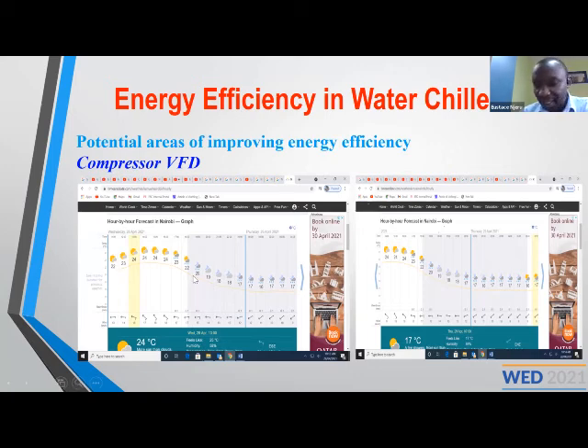You find that most chillers don't operate at full load always, because their operation is affected by the requirements of the cooling rooms and the external temperatures. For example, if it's a data center or a hall, and the hall is not full, say you started with 100 people and the number is reduced to 80, the cooling load will go on reducing. So you need to be monitoring the cooling load.